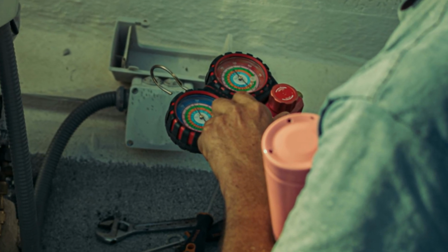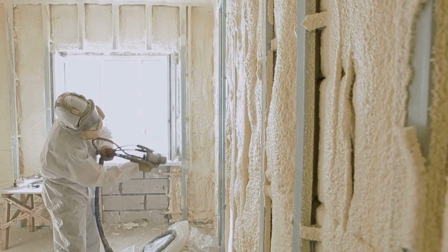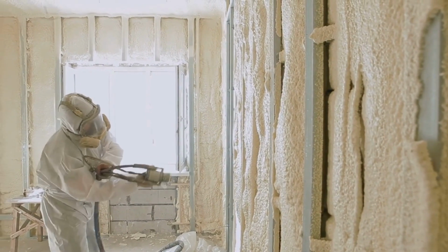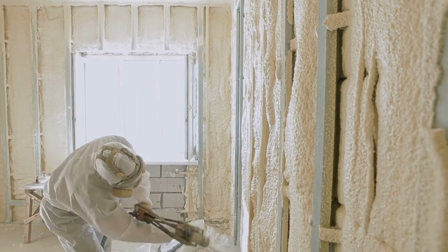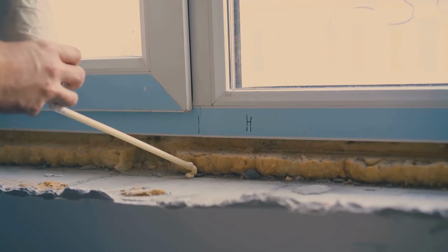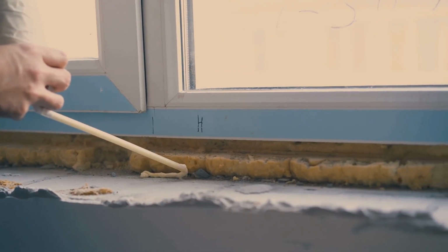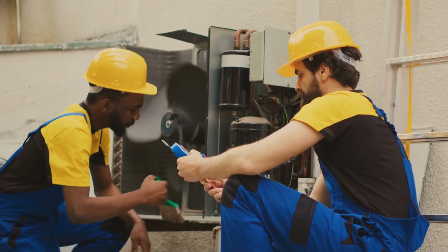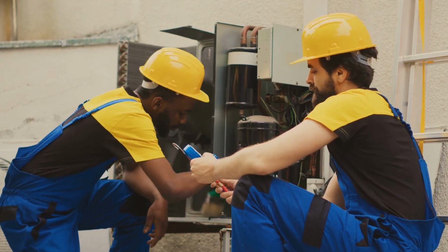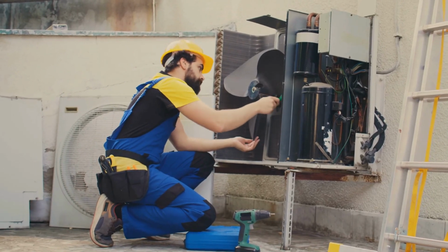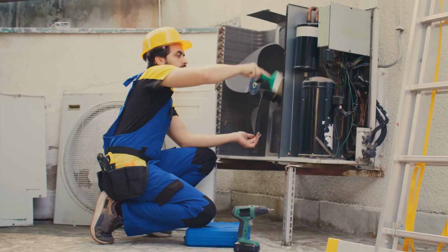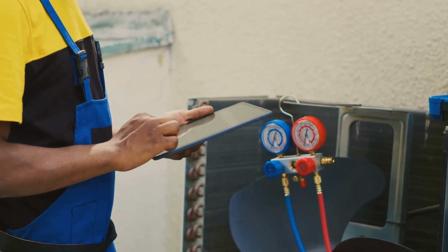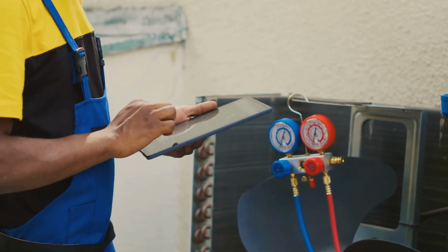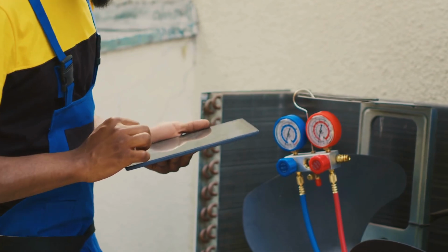Next, seal around openings. Use expanding foam insulation to fill any gaps or openings around the indoor and outdoor units where they pass through walls or ceilings. This step is key to preventing air leaks and improving energy efficiency. Then, secure the wiring and lines. Use cable ties or electrical tape to secure any loose wiring or refrigerant lines. This will prevent them from vibrating or rubbing against other surfaces, which could cause damage over time.